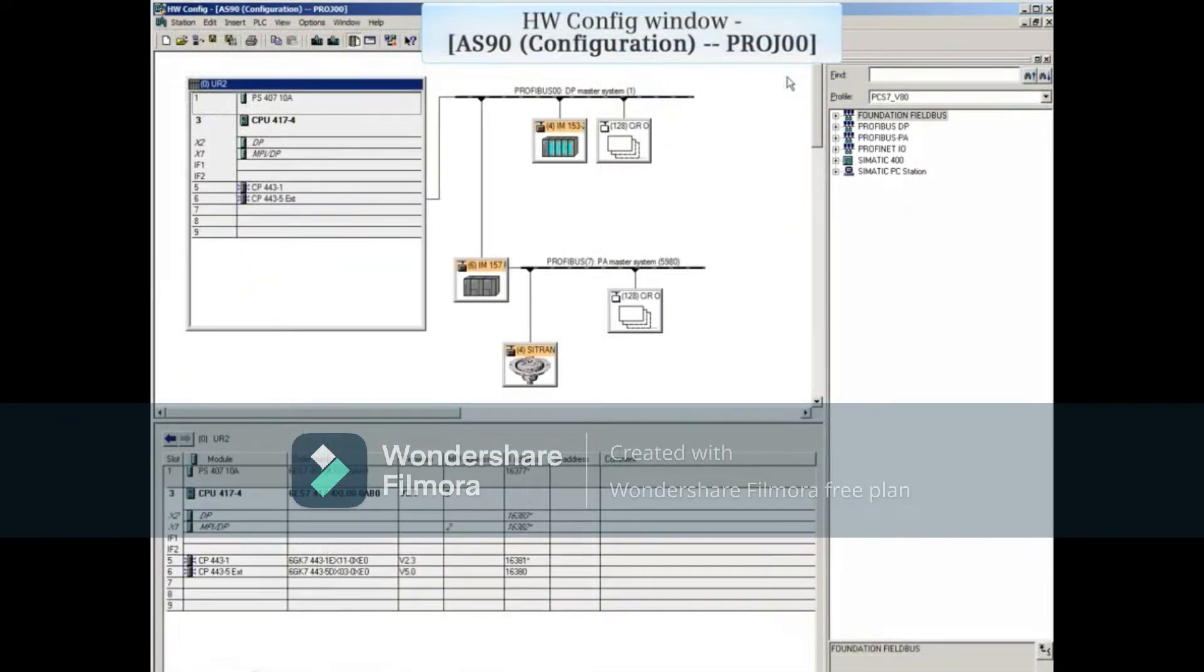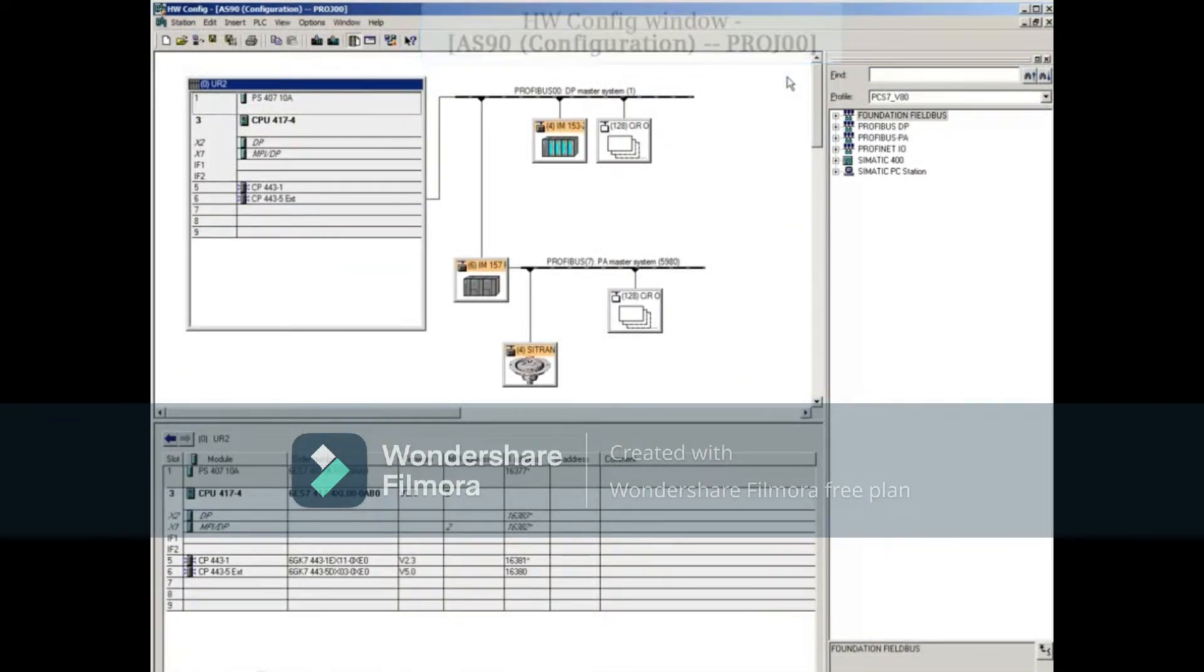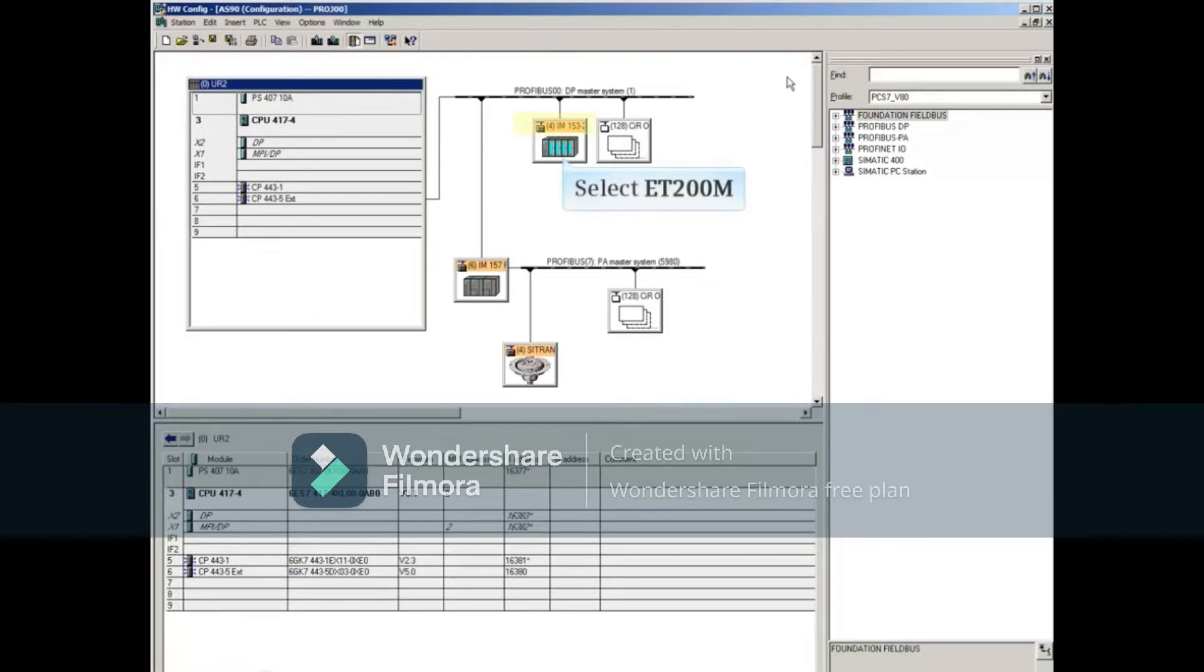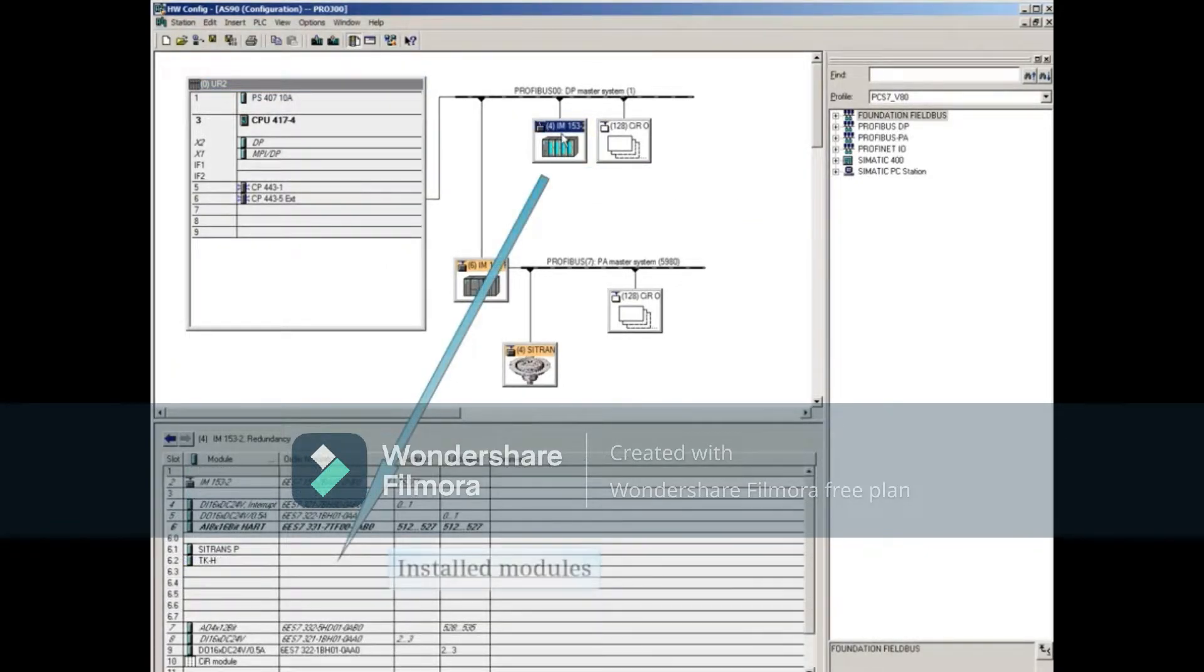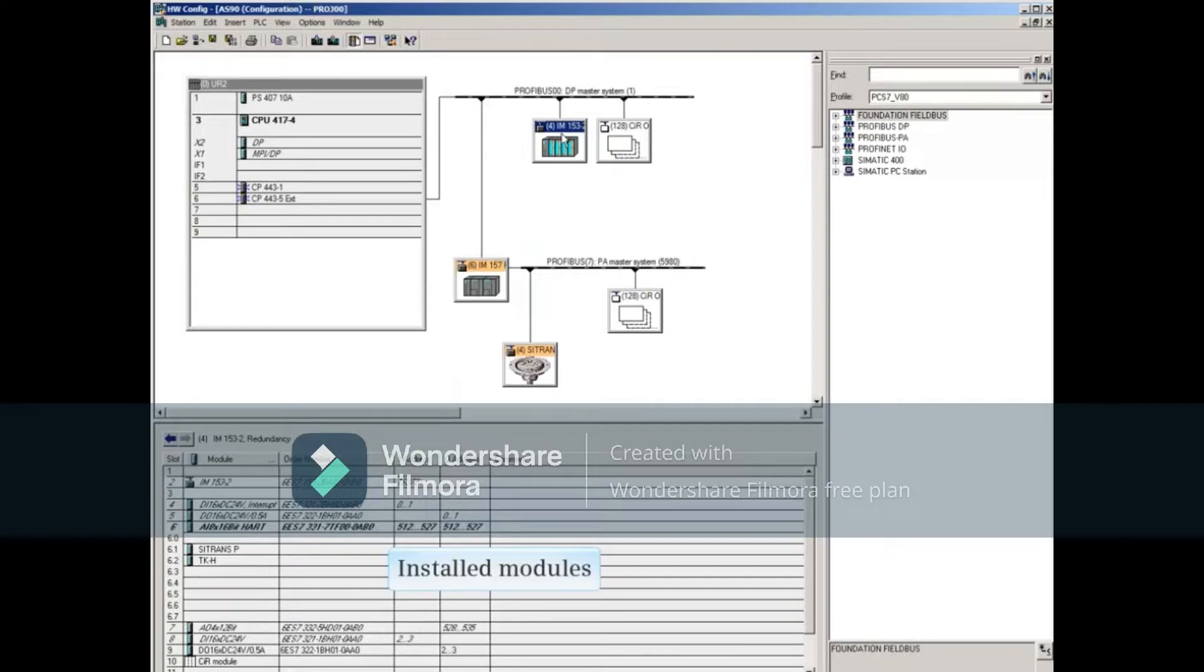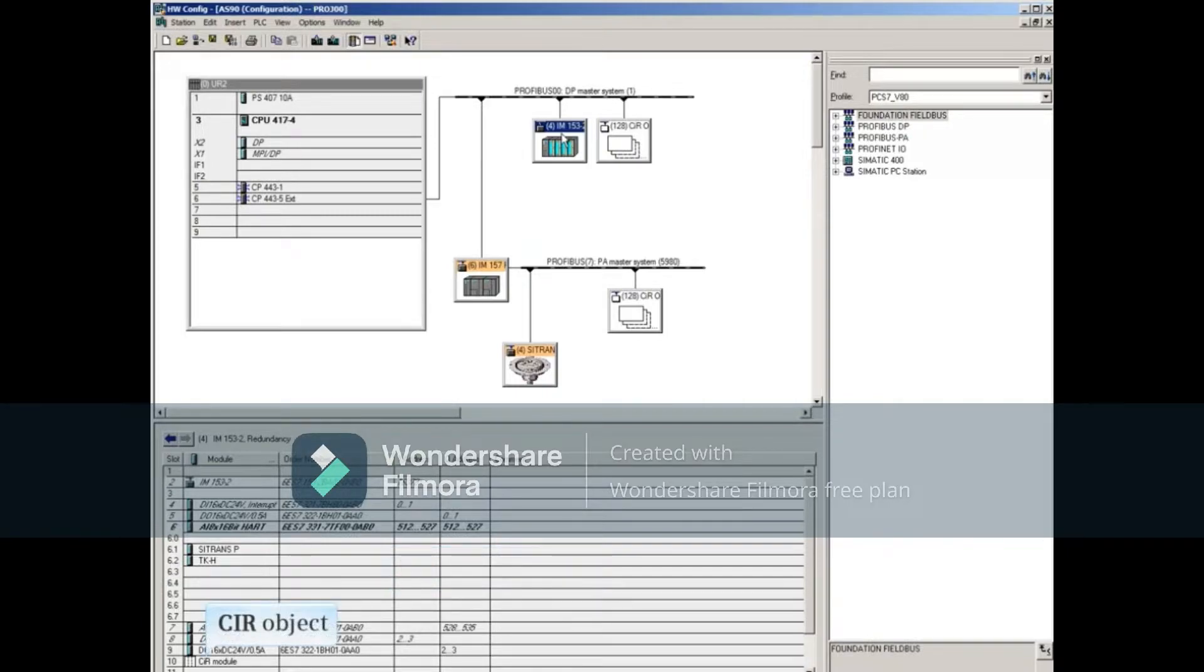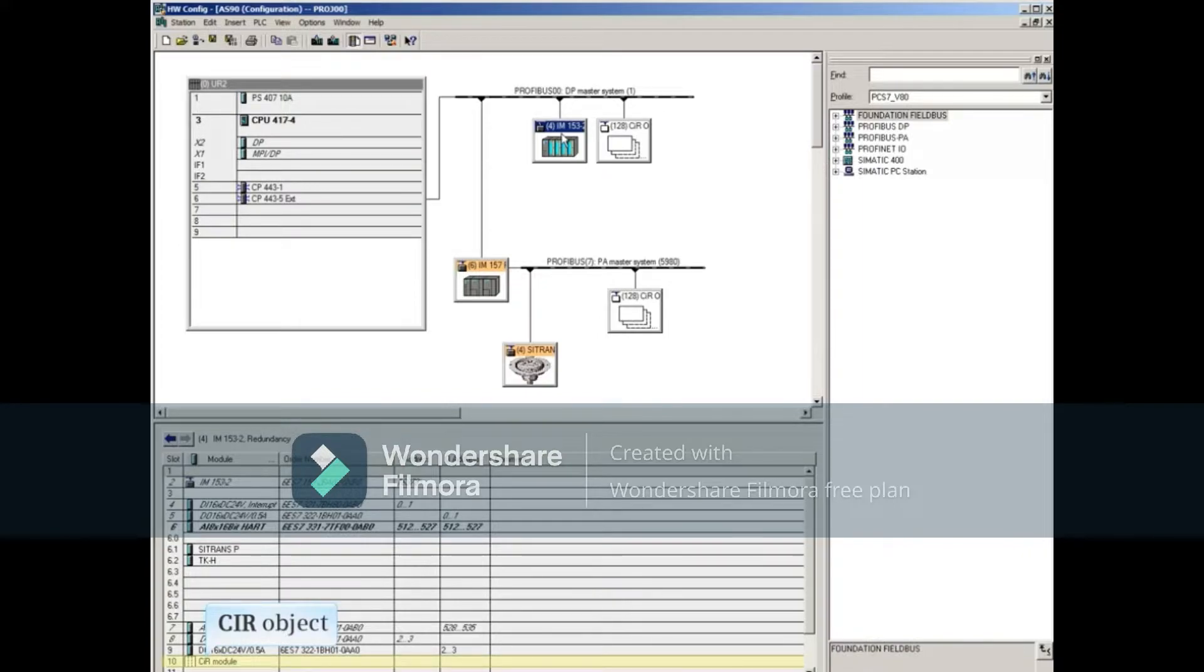This opens hardware configuration. For example, we plan on moving a channel assigned to a module in the ET200M. Selecting it will show the installed modules at the bottom. If the CIR object is at the bottom of the module list, then you should be able to download changes without stopping the CPU.